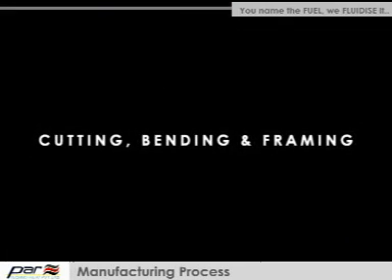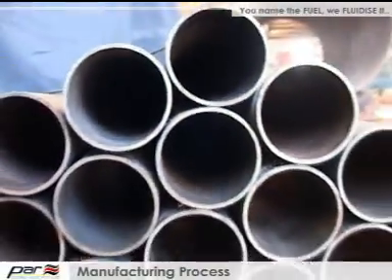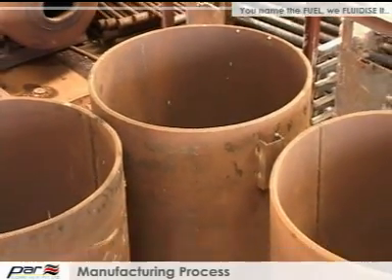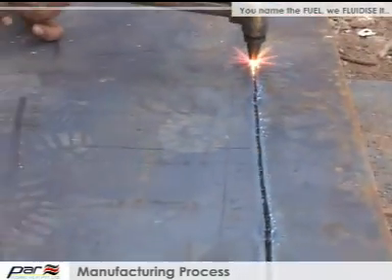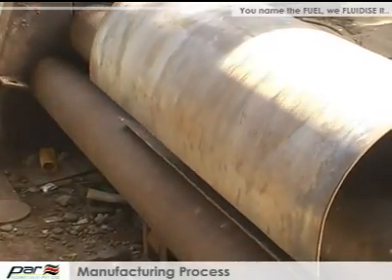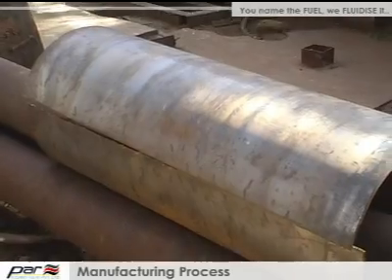Cutting, Bending and Framing — perfection is a way to excellence. After raw material inspection, plates and tubes are taken for marking, cutting and machining. Steel plates and tubes are marked and cut to the required size by gas-cutting torch or plasma-cutting machine. Plates are rolled and bent on a plate-bending machine. Tubes are bent on a hydraulic-bending machine to ensure proper size and shapes.